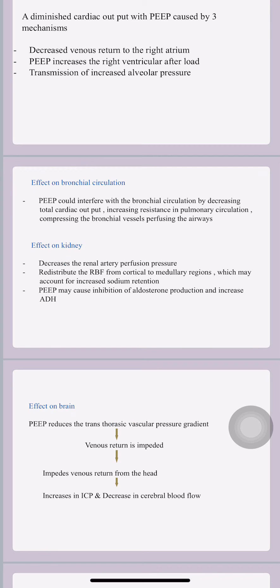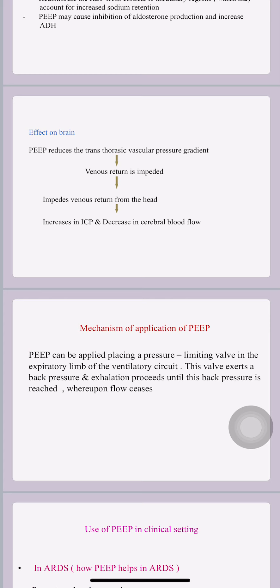So next is the mechanism of application of this positive end-expiratory pressure. PEEP can be applied by placing a pressure limiting valve in the expiratory limb of the ventilatory circuit. This valve exerts a back pressure, and the exhalation proceeds until the back pressure is reached, where the flow rate ceases. So that is the mechanism of application of PEEP.